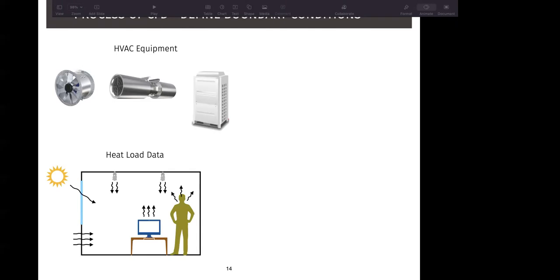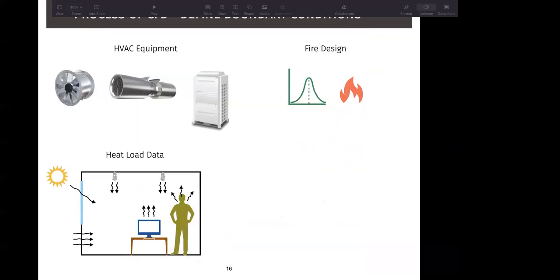For a thermal comfort study, we also look into the heat load data. So heat being generated within the system. In that case, we have to look into the solar radiation through the windows, the walls, the ceiling, the heat generated by any equipment within the room, by the number of people within the room, and by lighting or electrical components within the room. I'm sure you're familiar with the heat load sheet, where you can calculate the amount of heat flux through each component, from walls, from people, from equipment, light, appliances, and the same then becomes the boundary condition for your problem, and you can apply it to your given conditions.